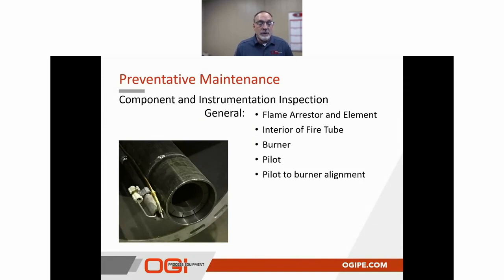The next step that we're going to take is we're going to review the pilot to burner alignment. When assessing this, we want to ensure that all pilot tubing and burner piping inside the flame arrestor are tight when we're finished. But in doing so, we want to ensure that that pilot is properly aligned with the head of the burner to avoid any potential disruption or instability caused by the main burner on the pilot. So it's kind of an important part, since we're trying to maintain that pilot stability, and that seems to be the heart of the operation of the unit.